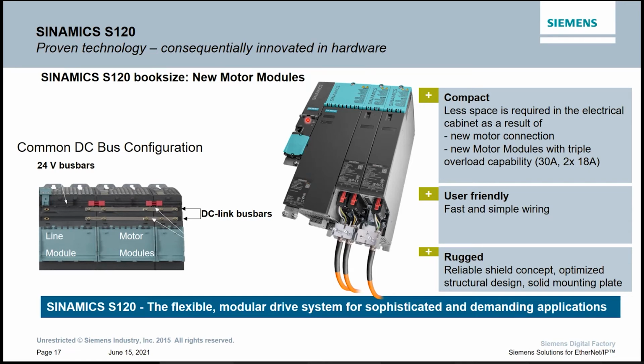This control unit here is where all the brains are. If something happens again from a power situation, whether it's the motor module or the infeed module, you can change out one of these components, not the whole drive system, and all your parameters, all your setup, all your programming is kept inside this unit. This control unit can be mounted up to about 100 meters away because it's just a network cable.